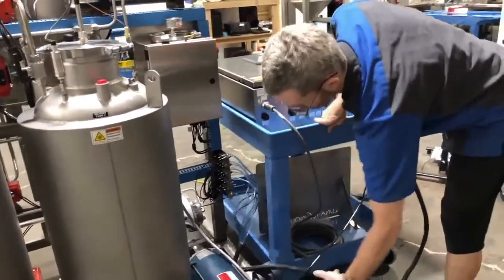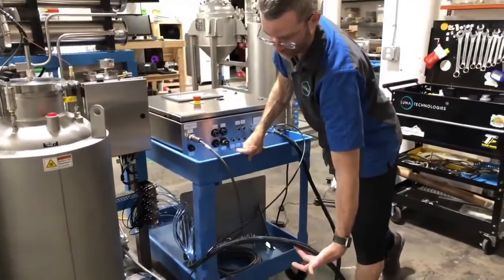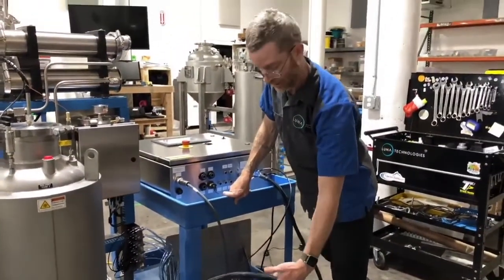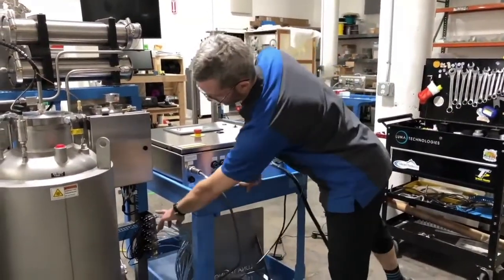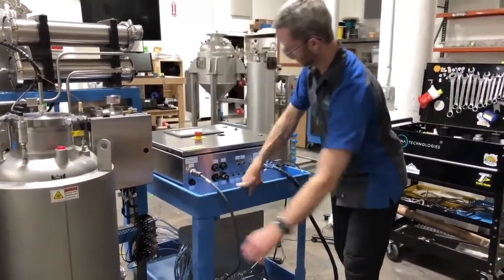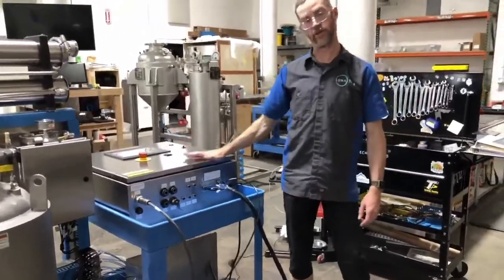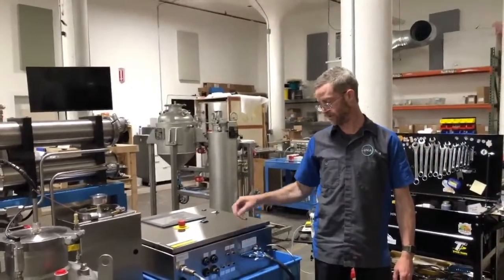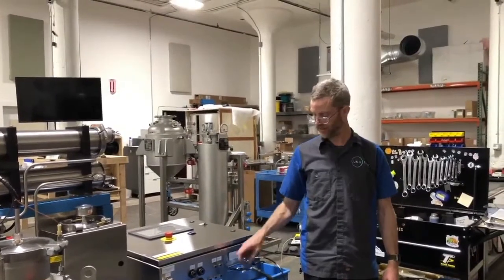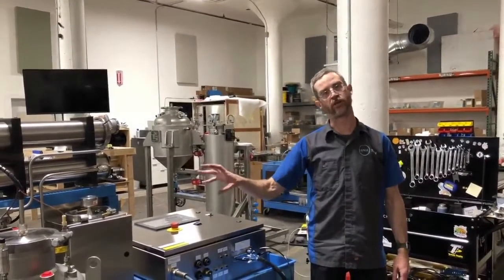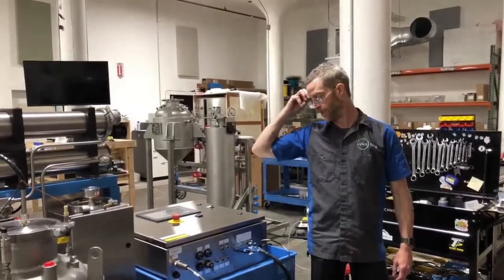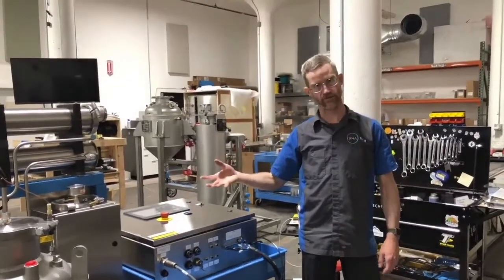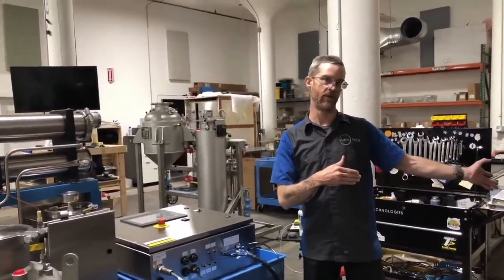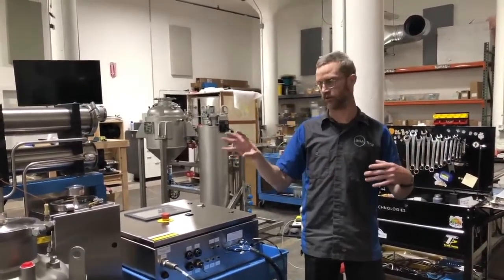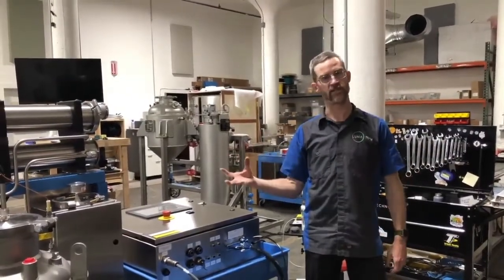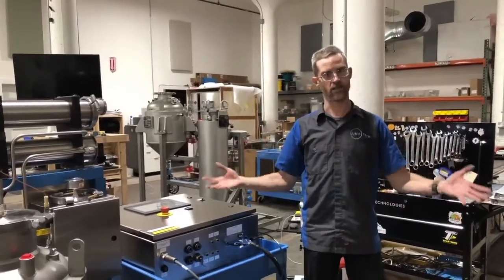And then this harness here is strictly for pressure testing. It just runs from the pneumatic bulkhead on the extractor to the pneumatic manifold on the control panel. And this actually sends little bursts of air through these lines to open or close the valves as necessary. The reason we do pneumatically controlled valves goes back to that C1D1 and hydrocarbon gas. We don't want electrical current to cause a spark. Pneumatics can't cause a spark.